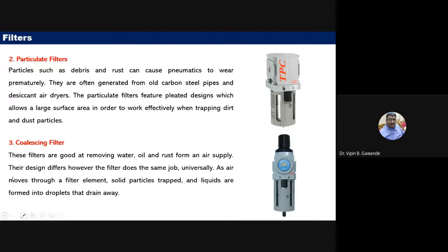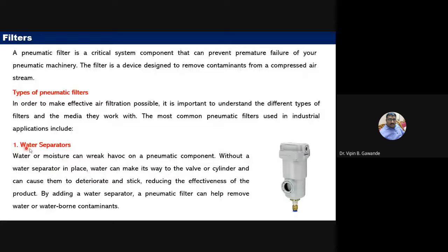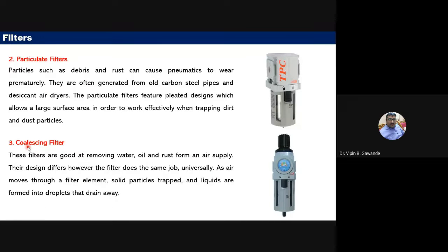The third type is the pneumatic coalescing filter. These filters remove water, oil, and rust from the air supply. As air moves through the filter element, solid particles are trapped and liquids form into droplets that drain away. The coalescing filter combines the functions of both a water separator and a particulate filter.